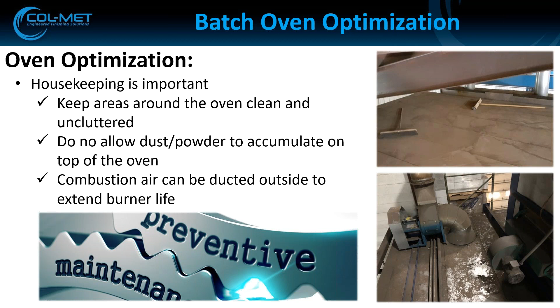One way to help reduce that is to duct the combustion blower outside of the building. Just keep in mind that if you do that, you want to make sure that the duct is bigger than the inlet, and try to keep the turns to a minimum, because you don't want to restrict the blower by adding additional static pressure.